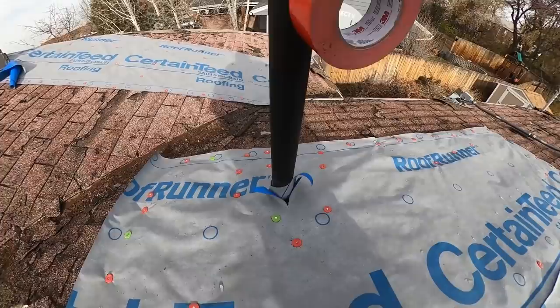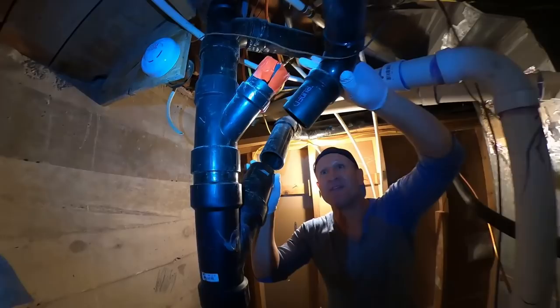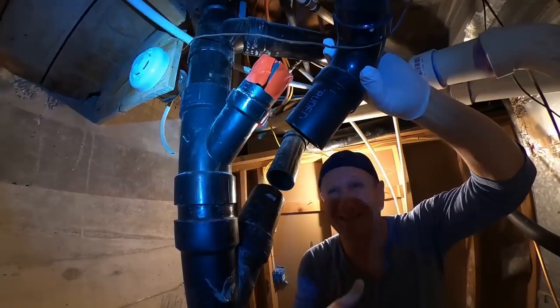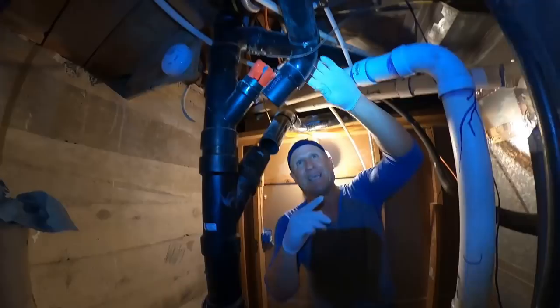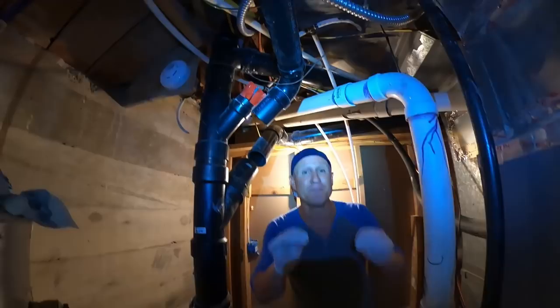Up on the roof we found something — this pipe is really loose, like it's disconnected. We've got the kitchen line that's completely isolated. We've capped off the top and the bottom. So now we're going to inject smoke into this pipe on one side of the plumbing system to fill up that section — that's section two. Section three is actually the kitchen line. We've separated everything so when we inject our smoke, we'll be able to pinpoint which sewer pipe is causing the odor from getting into the HVAC system.